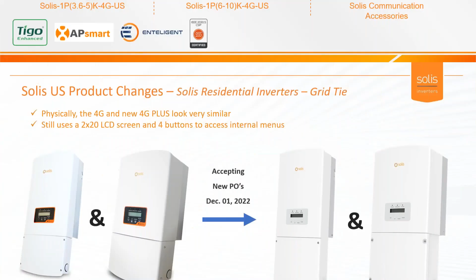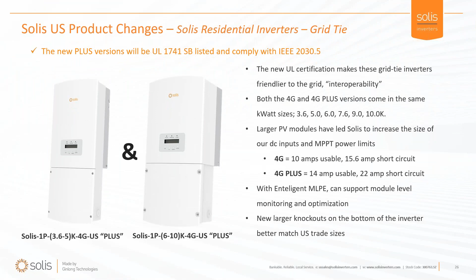The name is virtually the same, except we now refer to these new ones as the Plus versions. The reason is, you can see under that third bullet, the old 4th generation product could take 10 amps and go up to 15.6. But some of these new big modules put out even more than 10 amps. So when you're creating these PV strings, you want a new kind of input that can take higher power, a new kind of MPPT or PV string manager that can absorb these larger strings. And indeed, the Plus model can take bigger PV strings and more powerful PV modules.